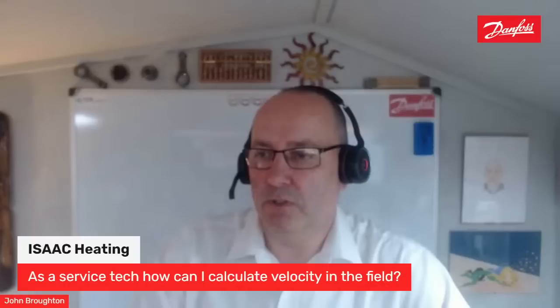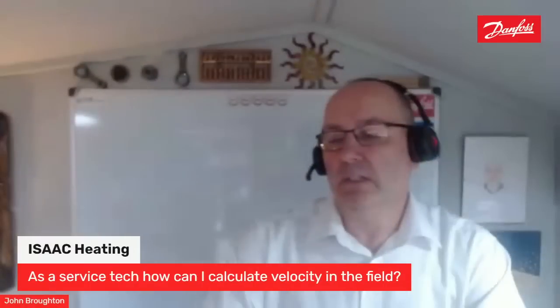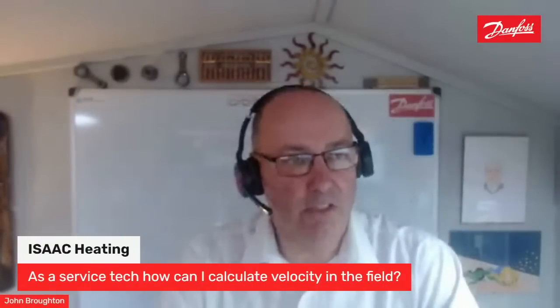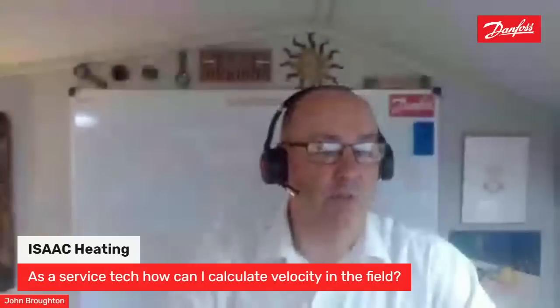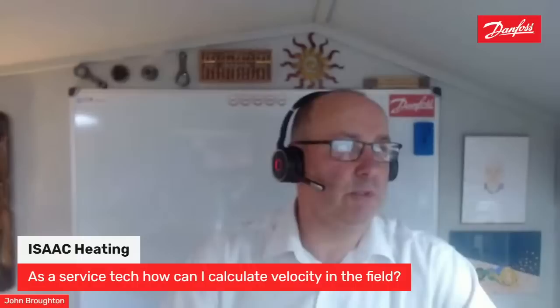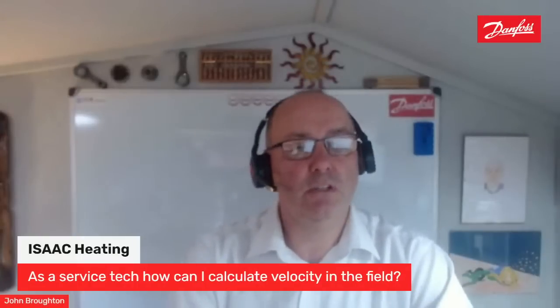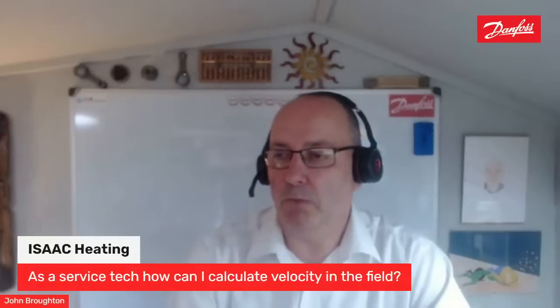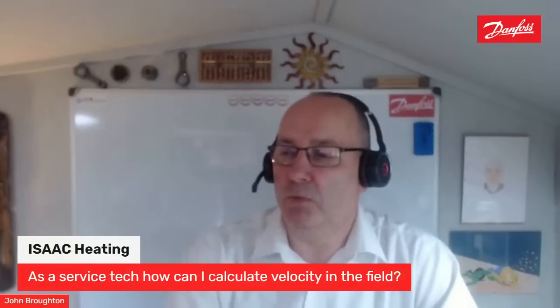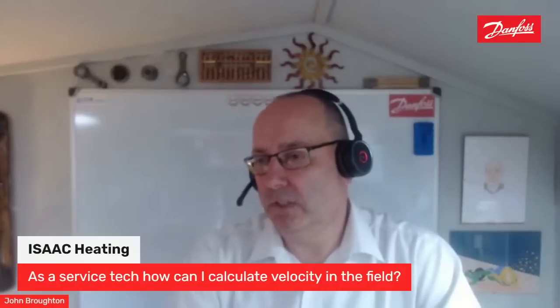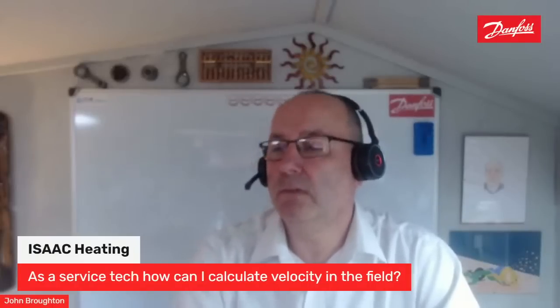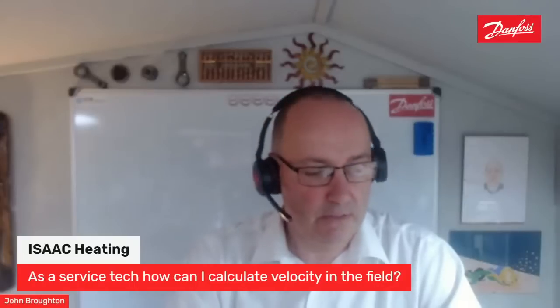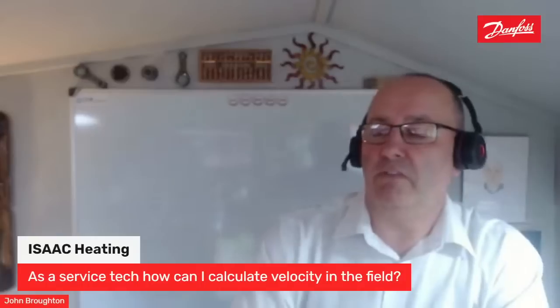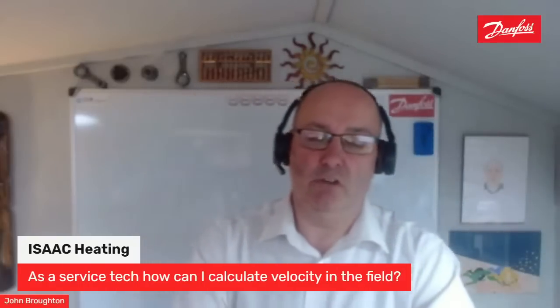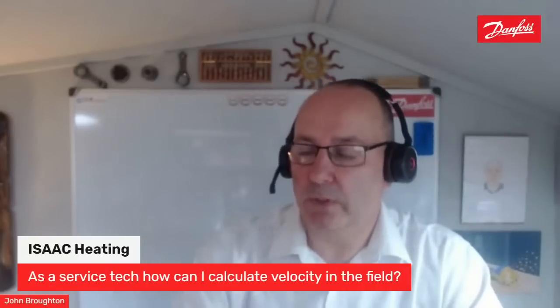A question from Isaac Heating: as a service tech, how can I calculate velocity in the field? I guess the simplest way, and it depends whether you've got a PC when you're out in the field, is that within Coolselector we do have a pipework section where you can put in the length of pipe, the duty, the evaporating temperature, and it will give you an approximate pipe size that you need on that piece of kit. I drag my computer around with me everywhere I go, and that's what I generally use.